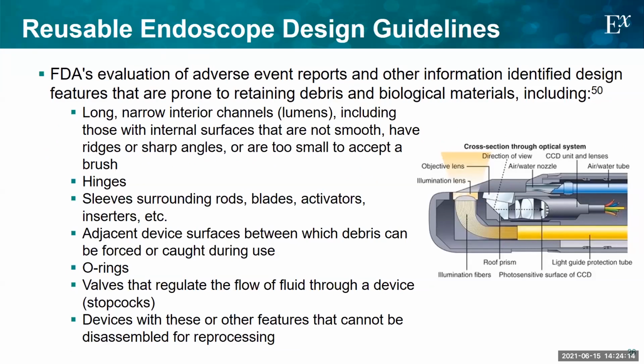Another thing that the FDA has weighed in very heavily on is the design of reusable endoscopes. And I'm just showing a picture here on the right, just to give you a sense that the tip of an endoscope is an extremely complex structure. And you can see there's lots of junctions between different materials. There's nozzles, there's ports where air can come in and out. Obviously, there's the optical system.